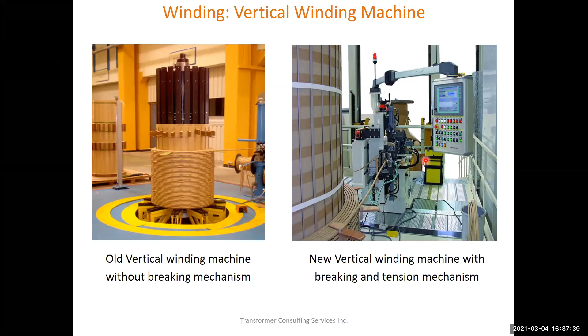to cause the failure. So now, here you see on the left-hand side picture, the winding has been removed from the winding machine, and I was doing the inspection, and you see how much space there is. So much space that even my pen can go through it. Because there is a space, what will happen in this space? If there is a repeated through fault, this conductor will get the space to move around. If it gets the space to move around, it will cause the failure of the transformer.